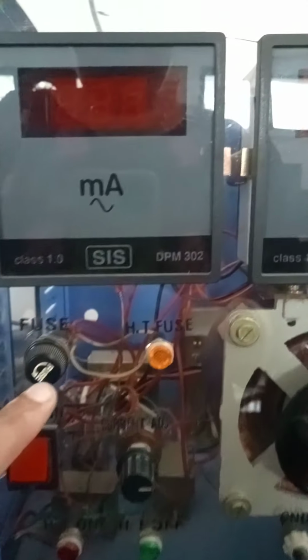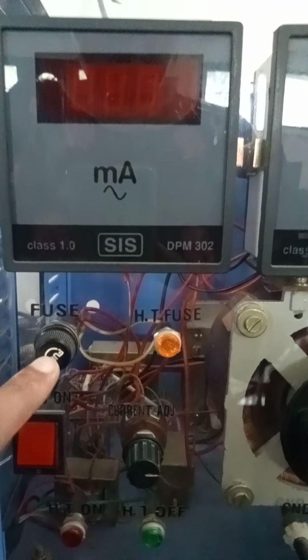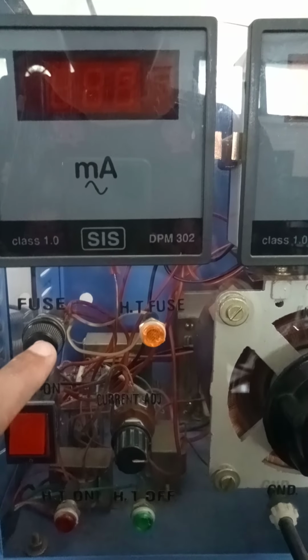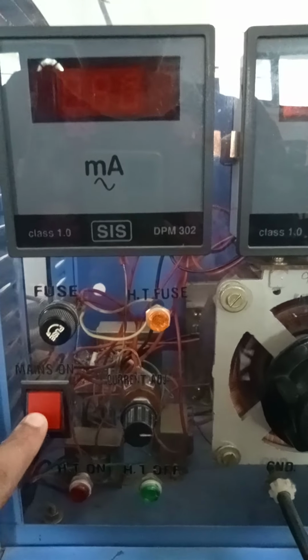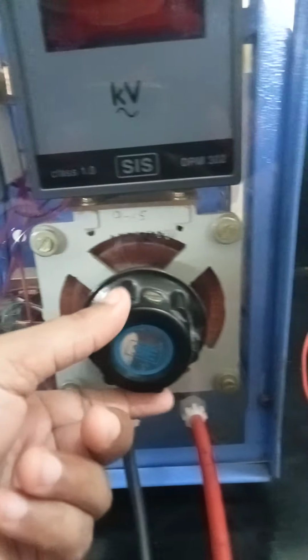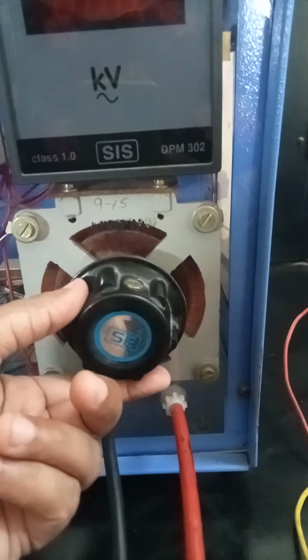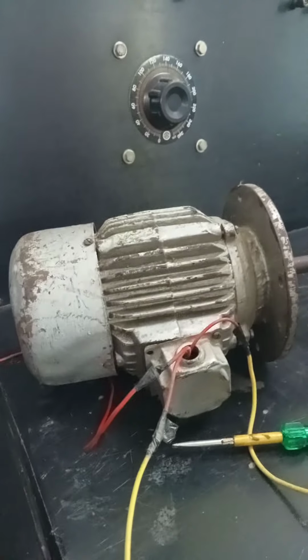Now as you can see, there is a fuse provided here. So in case of a short circuit, if there is an over voltage or over current, this fuse blows. This is the on mains. This is used to adjust the current, and this is a variac which is used to adjust the voltage. These are the two electrodes. So one electrode will be connected to each phase, and one electrode will be connected to the body of the motor. Now we will see how to perform this experiment.